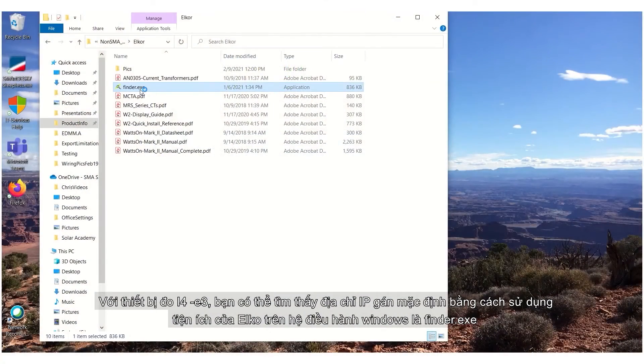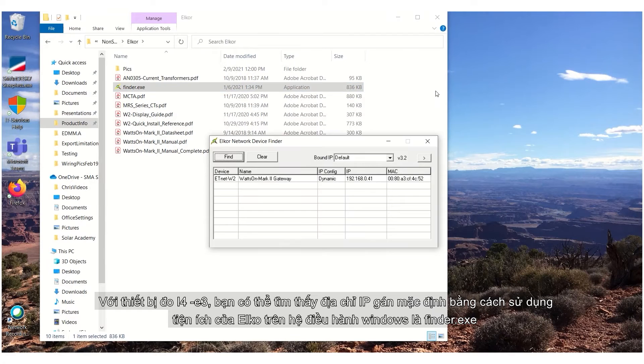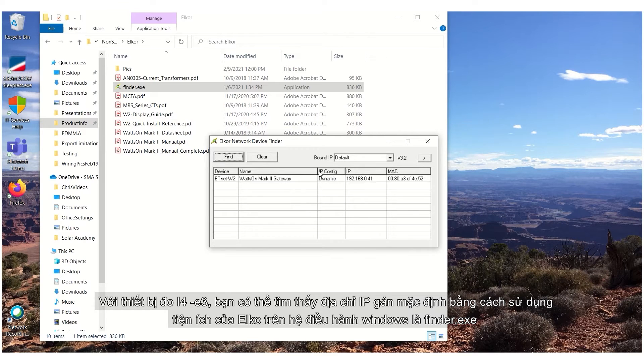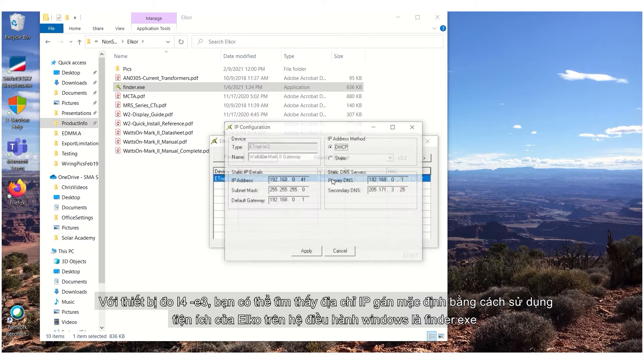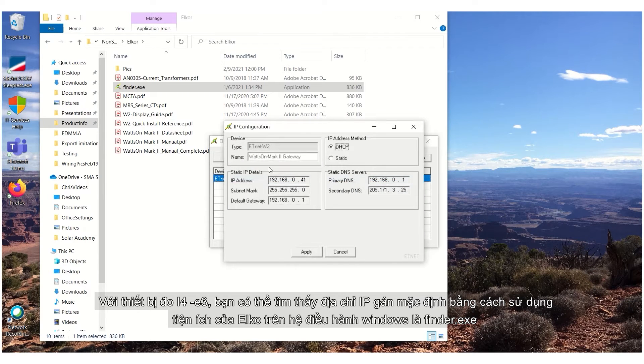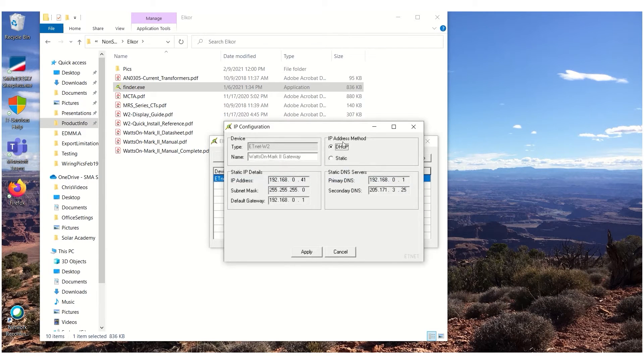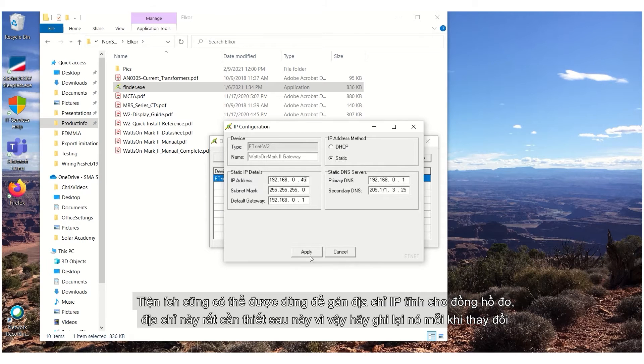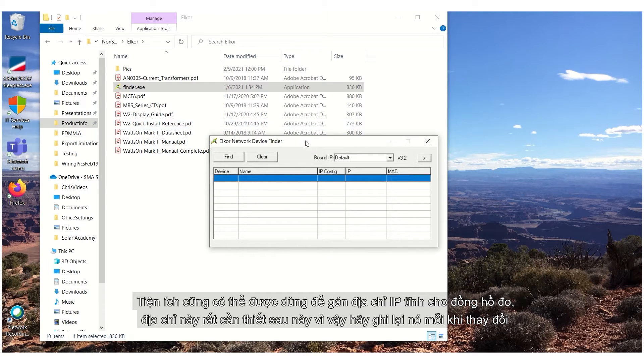SMA recommends setting the energy meter to use a static IP address. For the Elcor meter E3 model, the IP address assigned by default can be found using the Windows-based Elkor utility called finder.exe. The utility can also be used to assign a static IP address to the meter. This IP address will be needed later, so document it.